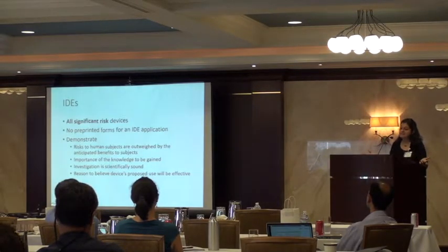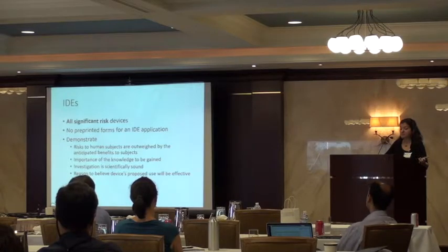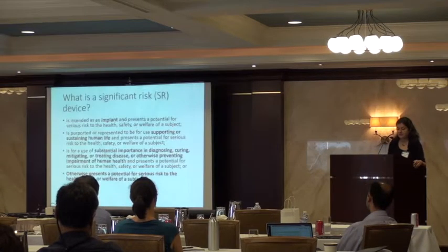So IDEs are needed for all significant risk devices. There are no pre-printed forms for the IDE, and you need to basically conceptually get across that the risks are outweighed by the benefits for the patients that will be in your trial, that the knowledge is important, that your study's sound, and that you have reason to believe your device will be effective.